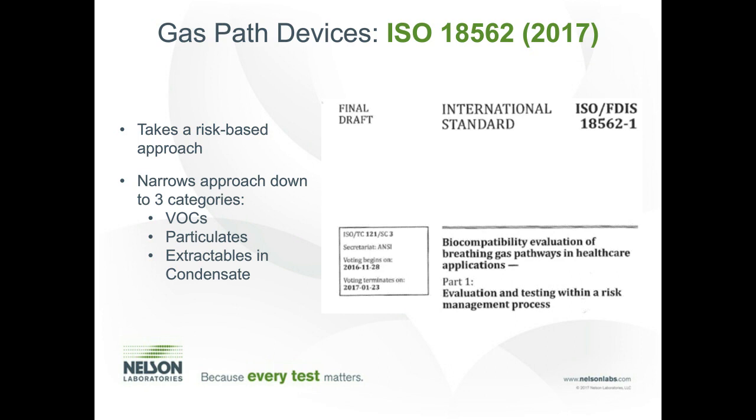With these gas path devices, I wanted to mention there's a new standard. It's ISO 18562. I was really excited that this standard came out because with respect to respiratory contact devices, we were seeing that the ISO 10993 series of standards really weren't fitting these devices very well.